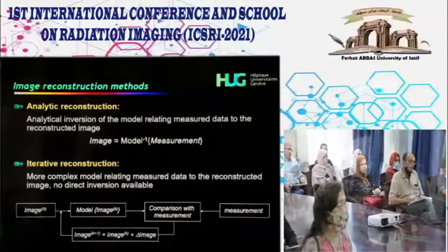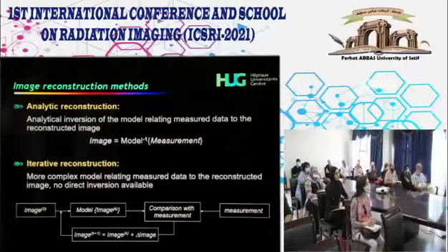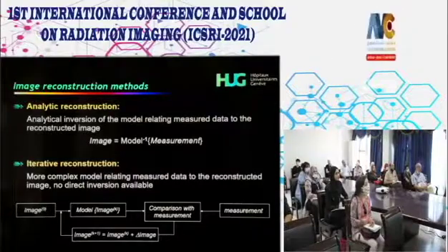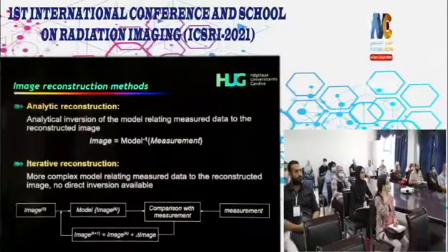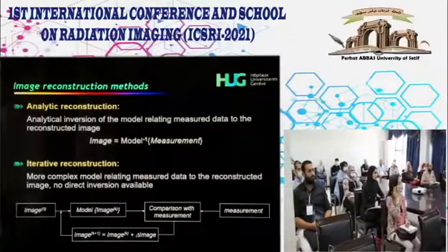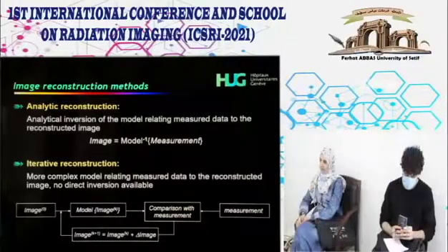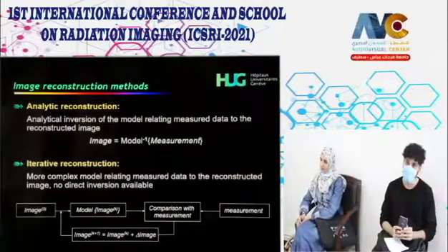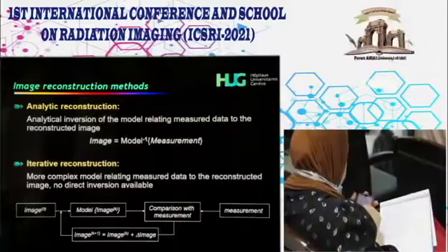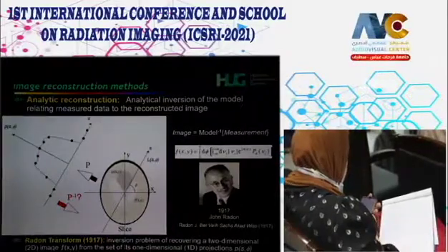Or a prior reconstruction that you get with filtered back projection, and then you forward project your images to get calculated projections that you compare to the measured projections, and then you've got a correction scheme here, which is really variable. So you've got some correction mechanism that updates the images, and the reconstruction is obviously iterative, so you do it as many times as needed, the number of iterations, to ensure that your algorithm converges. So this has been described, I think, in detail.